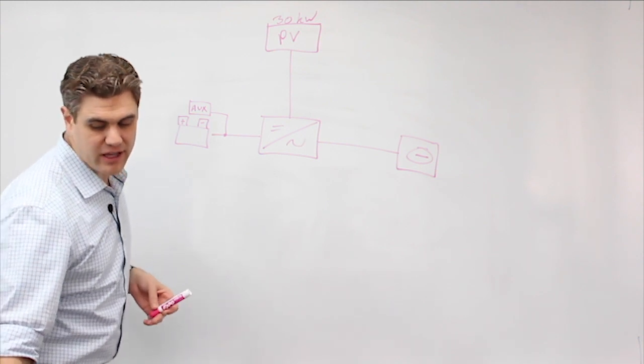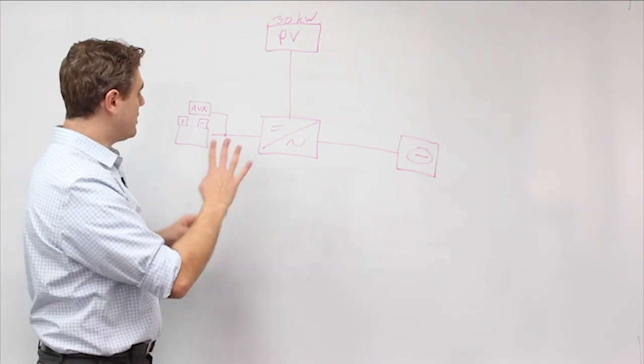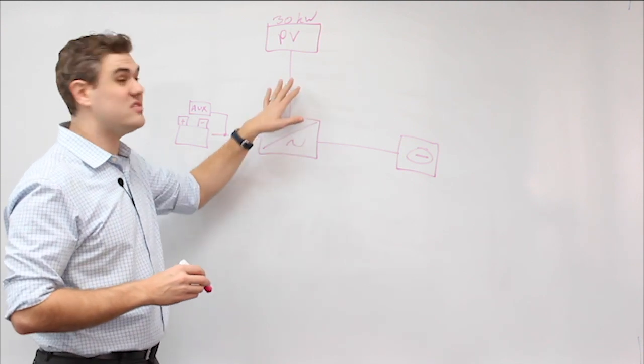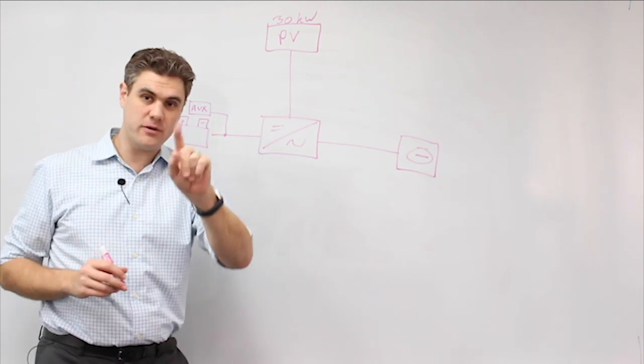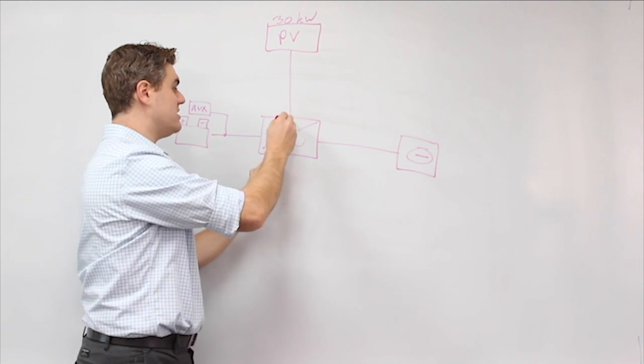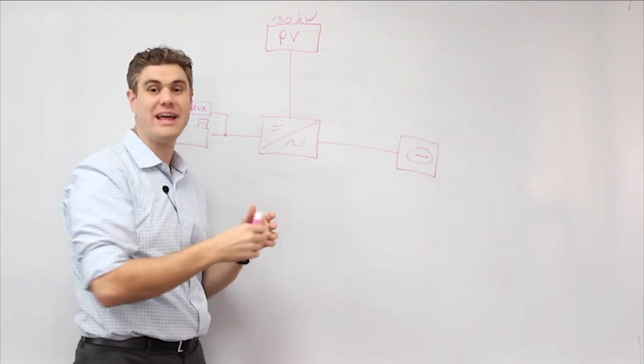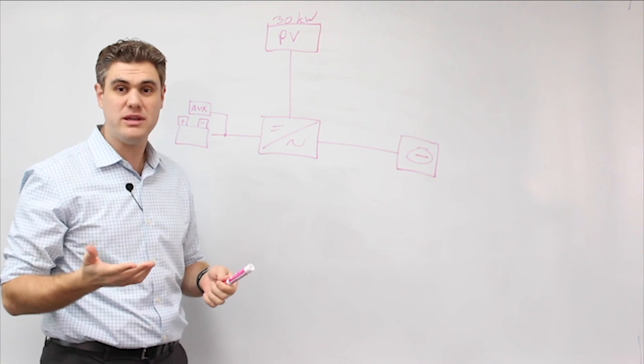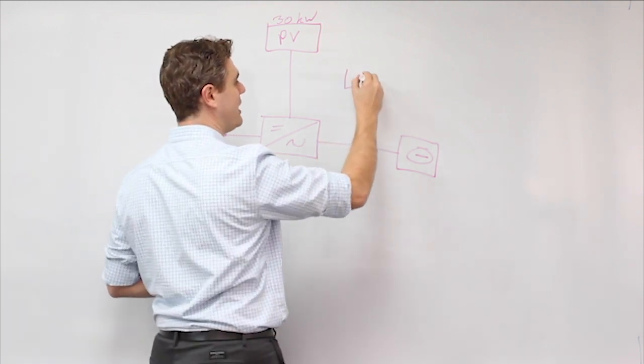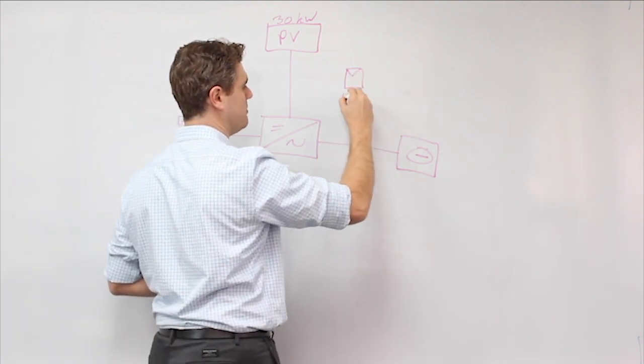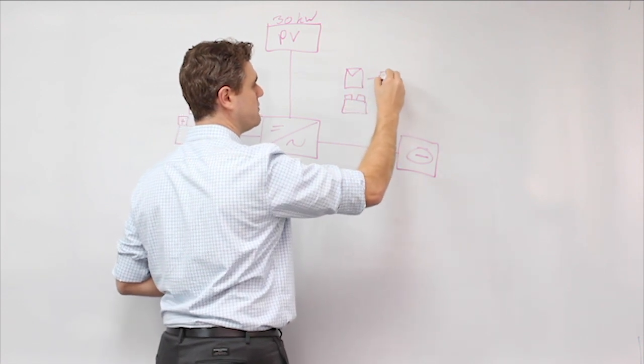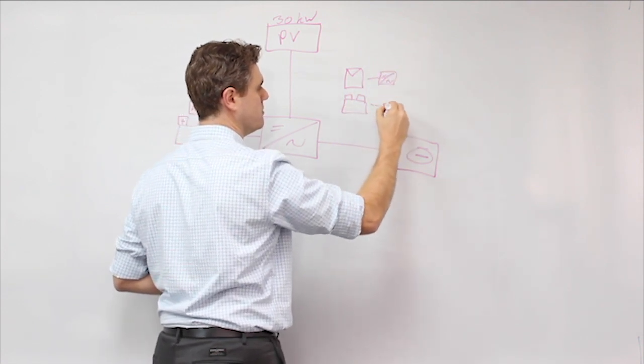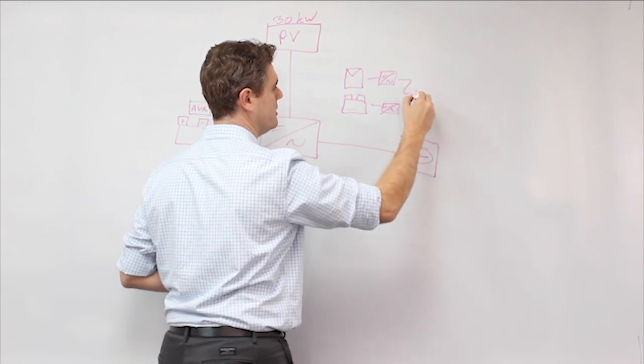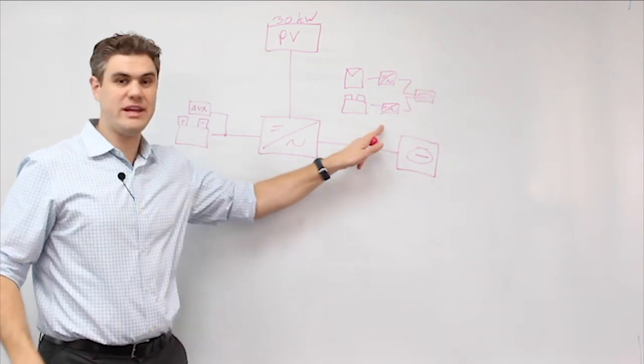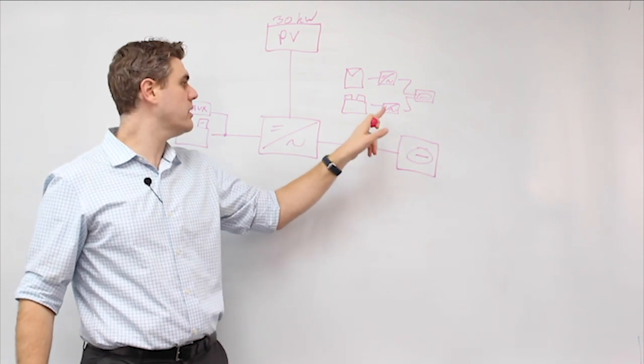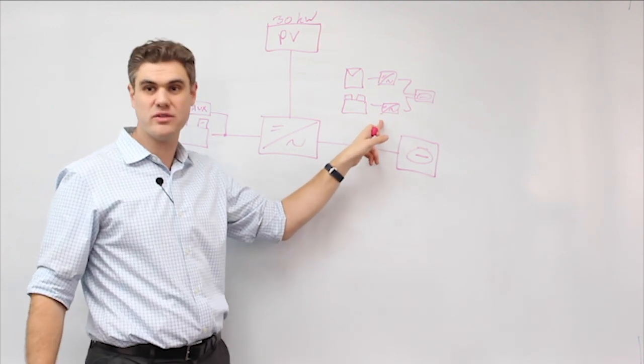So now let's take a look at some of the ways that this pair, and by the way, sorry, one last thing. This is DC coupled because there's one inverter. When you have solar and batteries connecting together on the DC side of an inverter, we call that DC coupling. The alternative would be AC coupling, right? Where you have a solar system and a battery system, and they both connect into their own inverters before they connect together into the utility grid. This is what's called AC coupling. Twice as many inverters, more efficiency losses, more cost, of course.